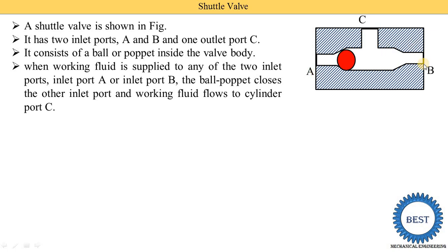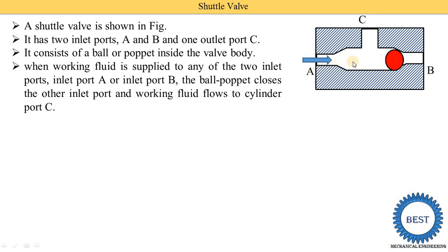When the working fluid is supplied to any of the two inlet ports — either A or B, or both — the ball or poppet closes the other inlet port and the working fluid flows to outlet port C. For example, when fluid is supplied from inlet A — whether hydraulic oil in a hydraulic system, or air or gas in a pneumatic system — the ball moves towards inlet B, closing it. The fluid from A is then directed to port C and supplied to the actuators.